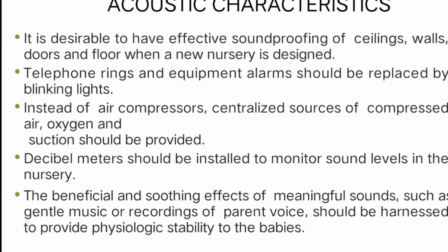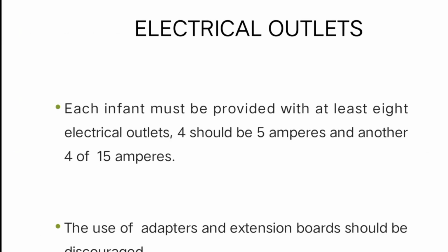Next we will be seeing about the electrical outlets. Each infant must be provided with at least 8 electrical outlets for easy access. For example, 4 should be 5 amperes and another 4 should be 15 amperes. The use of adapters and extension boards should be discouraged.